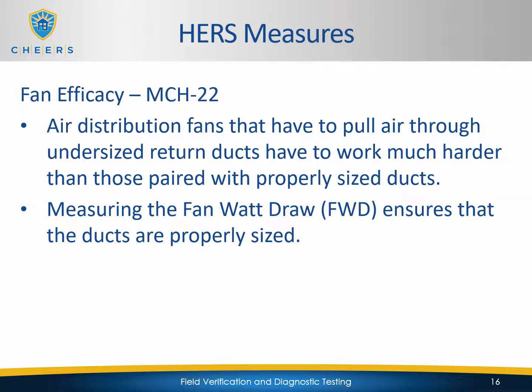So you can imagine, picture a straw. You have a really skinny straw versus a fat straw. It's much easier to suck a liquid up through a fat straw than it is a skinny straw. And so this works under that same principle. We want to make sure those ducts are properly sized so that the fan operates within its efficiency range and is not working harder than it needs to.